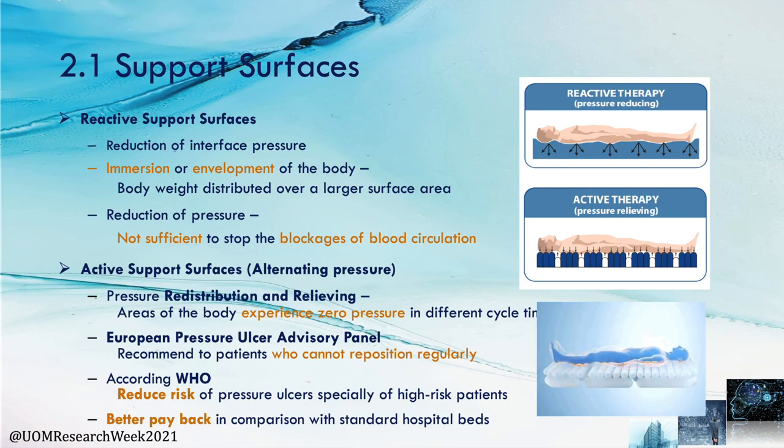Support surfaces can be categorized into two groups: reactive and active support surfaces. Reactive support surfaces reduce interface pressure by immersion and envelopment of the patient body, but still apply constant pressure, which is insufficient to stop blockage of blood circulation. Active support surfaces, also known as alternating pressure mattresses, redistribute and relieve pressure from high pressure localized zones. The European Pressure Ulcer Advisory Panel recommends alternating pressure mattresses for patients who cannot reposition regularly, and according to the WHO, these also reduce the risk of pressure ulcers especially for high-risk patients.